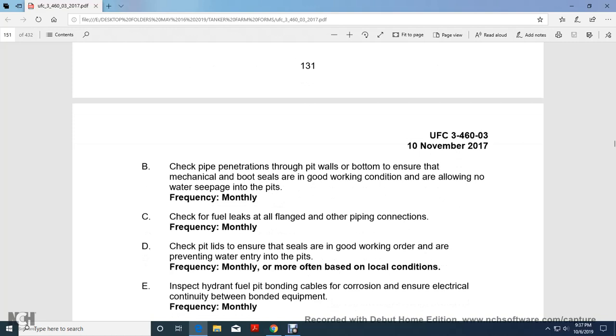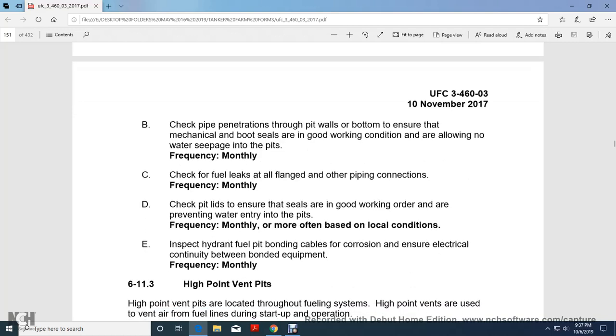Check for fuel leaks over the flange and other piping connections monthly, to ensure that the seals are in good working order and prevent water entry into the pits. Monthly checks are often based on local conditions. Inspect hydrant fuel pit bonding cables for corrosion and ensure electrical continuity between bonded equipment, monthly.